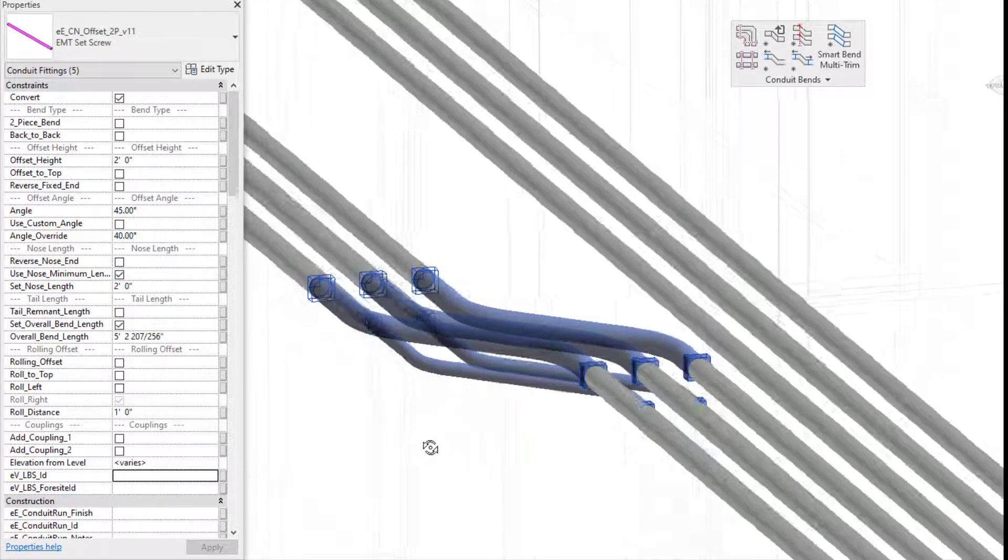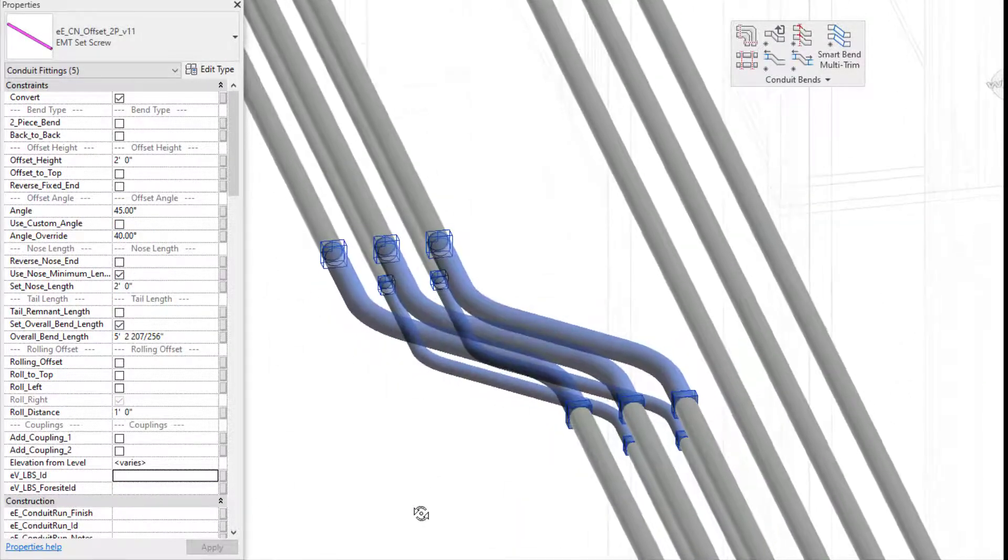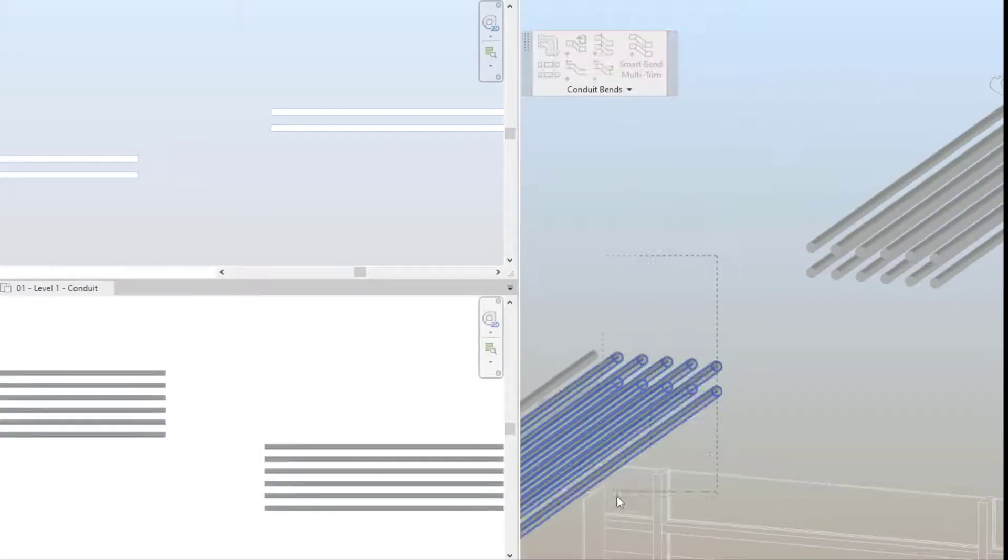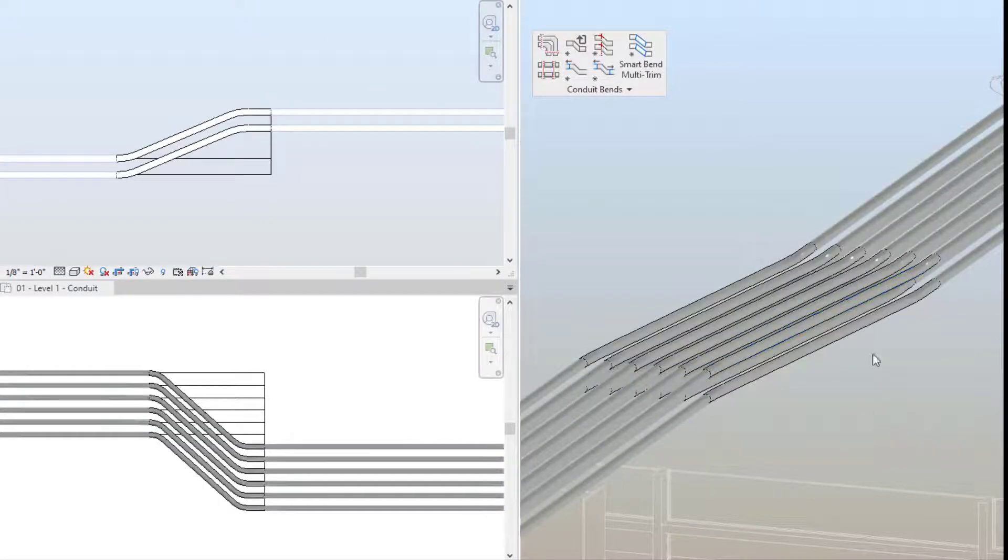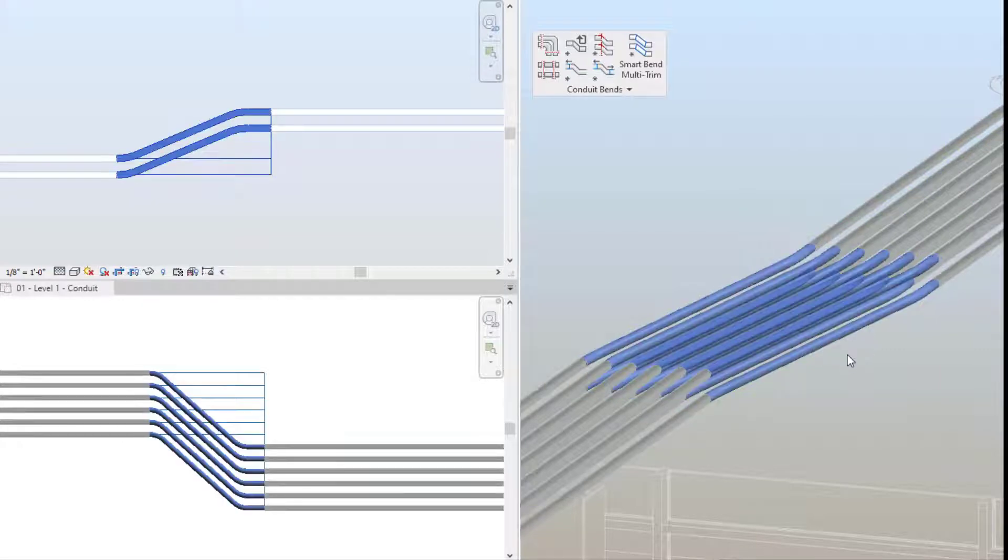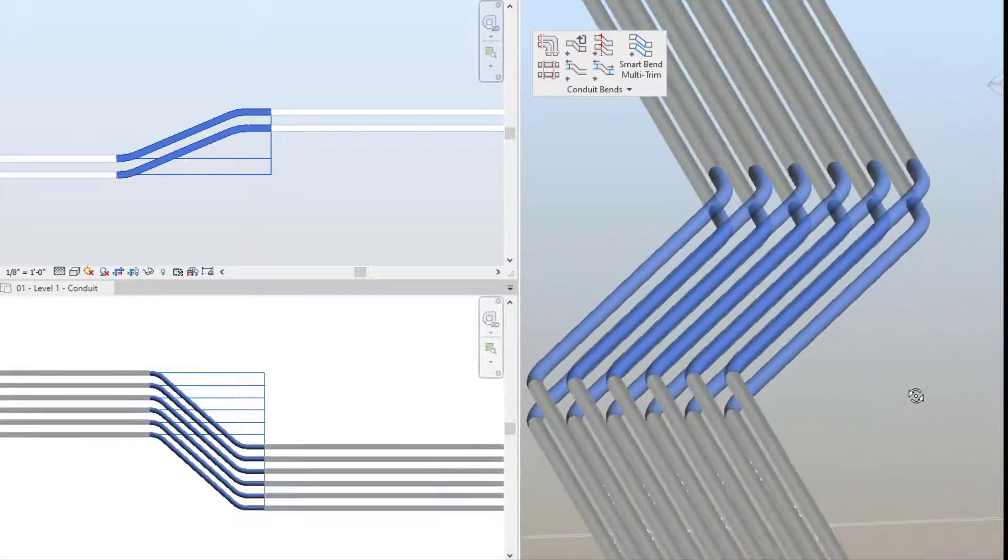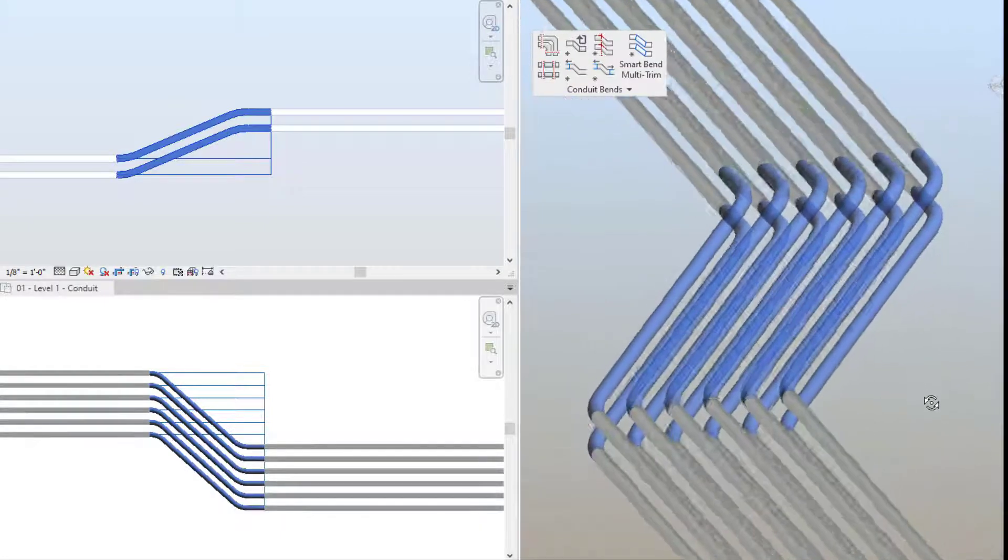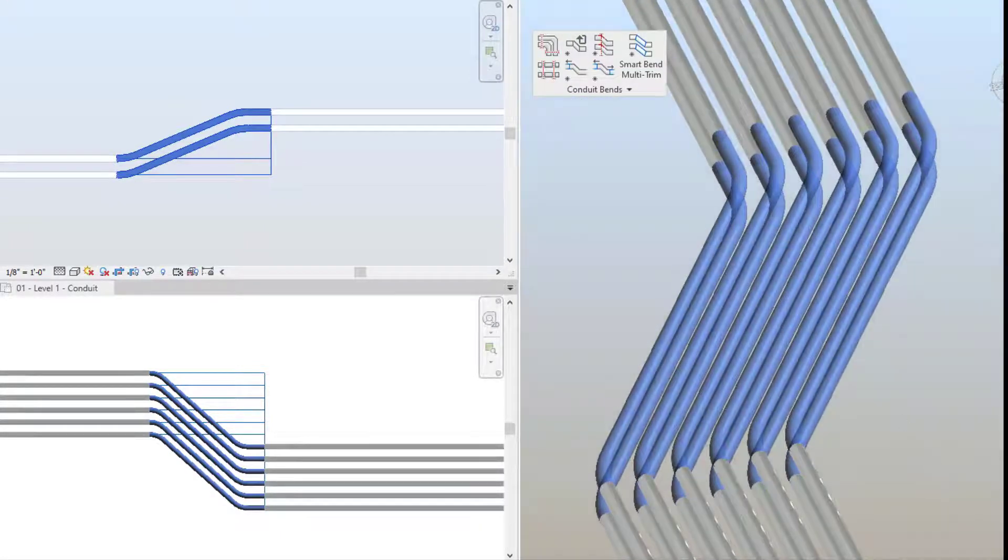The smart bend multi-trim feature allows you to connect one or more conduit runs together with an offset or kick 90. This feature is also awesome if you're getting Evolve Electrical mid-project and you have some native Revit bends still in your project, because if you hold down shift and select this feature, it will replace native Revit conduit offsets or kick 90s with Evolve Electrical smart bends.